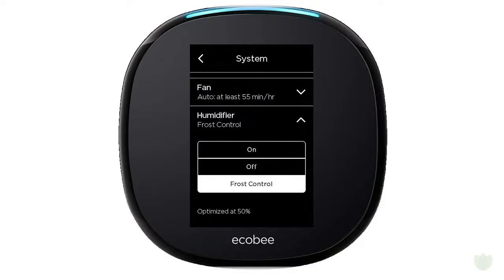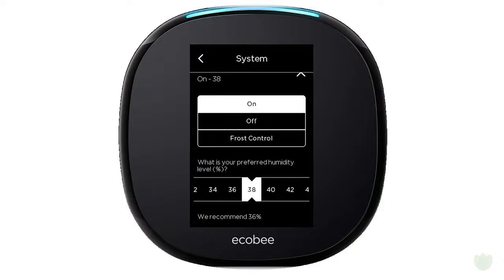With the humidifier, I've wired this thermostat up to utilize all stages. So it's a 2 heat, 2 cool with a heat pump. And we've also got a humidifier wired up. So with the humidifier, you're going to be able to go in and adjust that here, turn it on. It's going to ask you to set your preferred humidity level, usually somewhere around 40%. We recommend 36. It's going to depend a lot on the time of year.